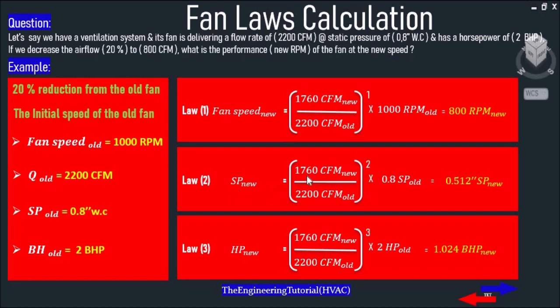Static Pressure New equals (1760 CFM New divided by 2200 CFM Old) squared, multiplied by 0.8 inches of water column (Static Pressure Old), which equals 0.512 inches of water column. The static pressure has changed from 0.8 to 0.512.